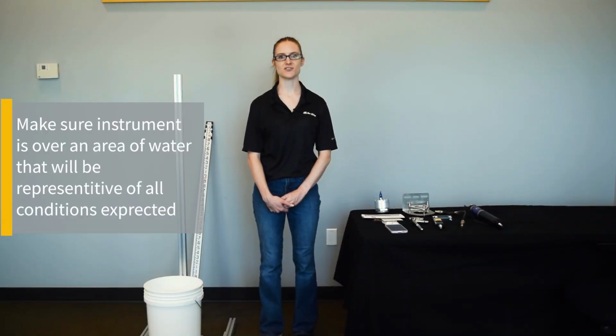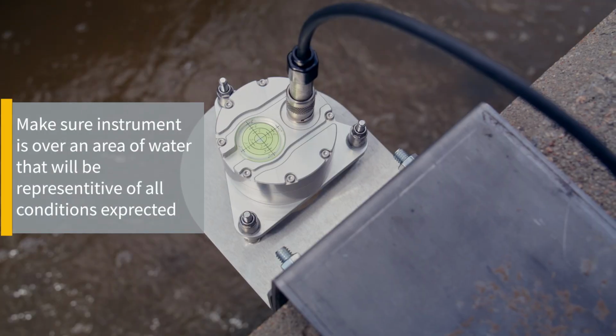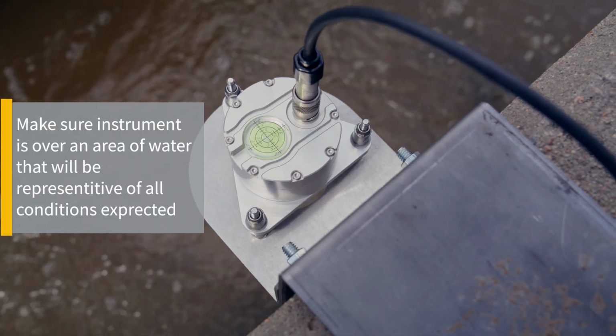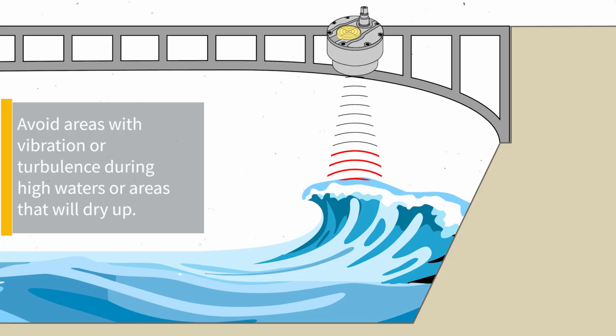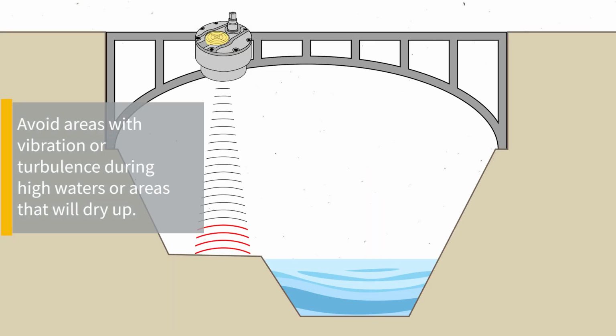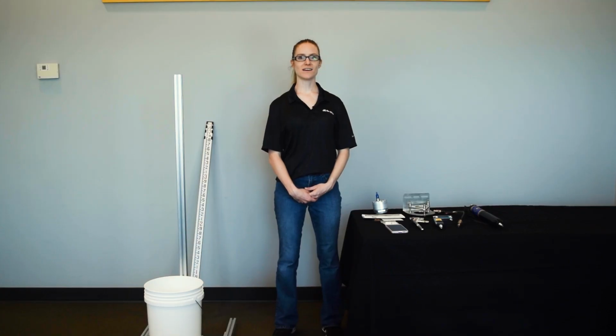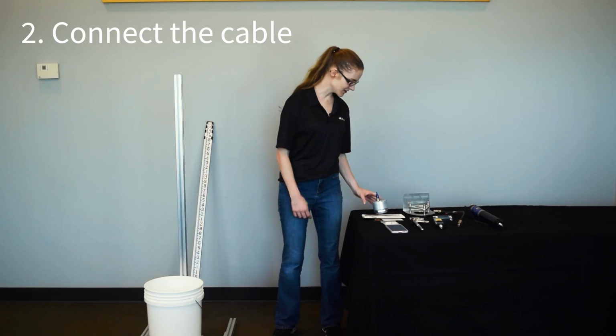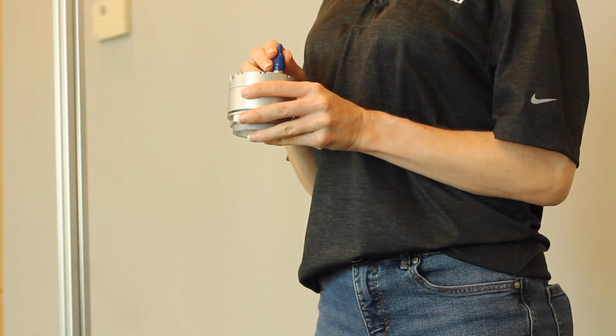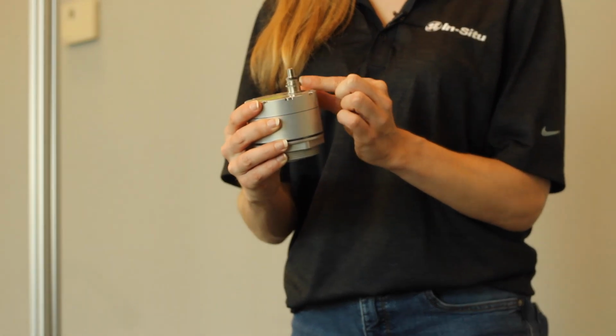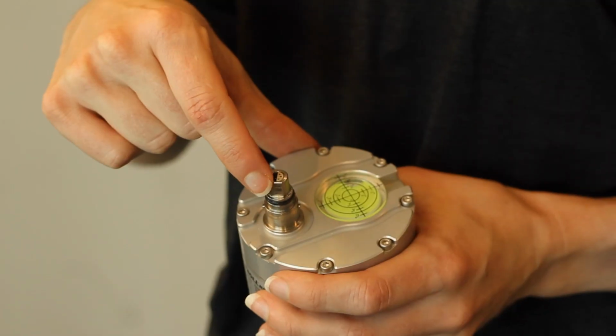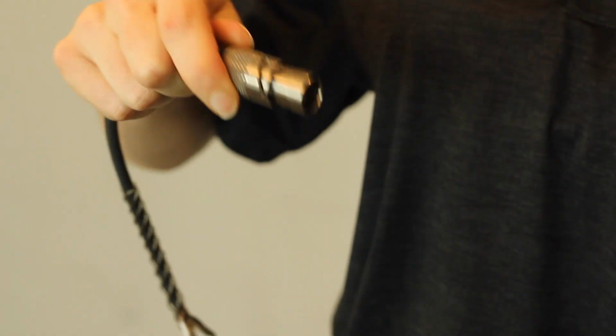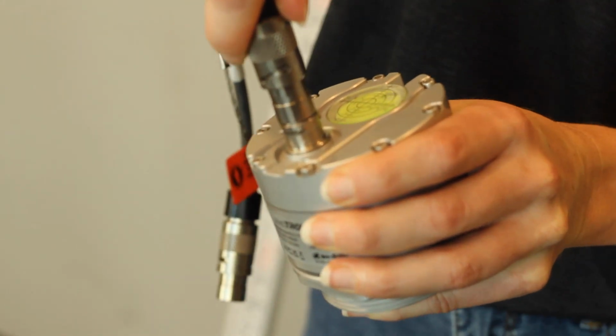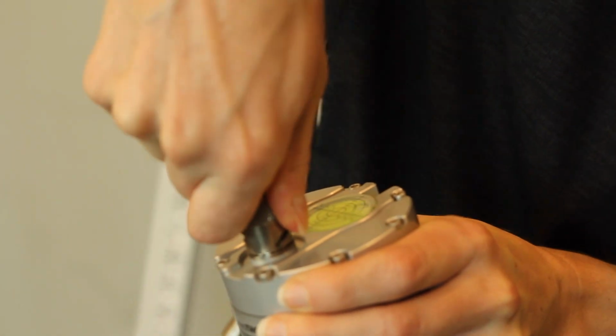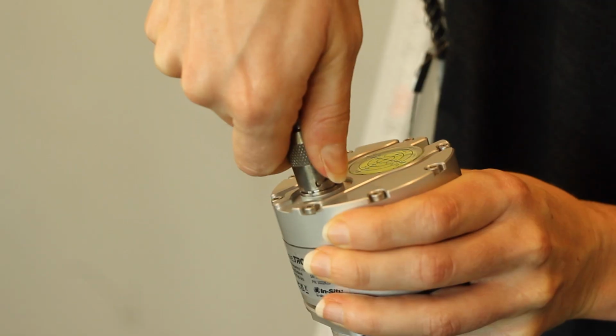Lastly, make sure the instrument is over an area of water that will be representative of all conditions expected at the deployment site. Avoid areas where there is a lot of vibration or turbulence during high water, or areas that will dry up when the water is low. Once you have the location selected, it's easy to connect your instrument to the cable. Remove the protective cap and apply a thin layer of grease to the O-ring. You'll see a flat surface inside the cable that mates with the flat side on the connector. Match these edges and then push and twist the cable sleeve until the connector clicks into place.